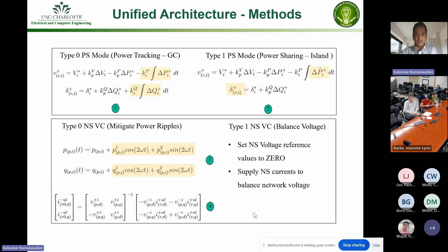So here is an example of a few results from this architecture. You can see on the top right, the proposed controller in the grid connected mode has current proportional to the voltage, and the current that has been supplied has a negative sequence component as required, as opposed to what is there in the literature, and it can also mitigate the harmonic content.